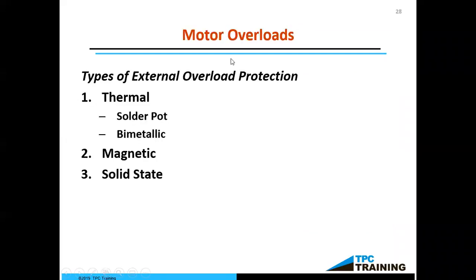The overloads are something that we might have to take a look at if our motor is giving us a little bit of problem with starting or tripping off all the time. They can be basically three different types. They can either be a thermal type of sensor, where it is going to determine how much heat is traveling in the circuit. So those are two different types.